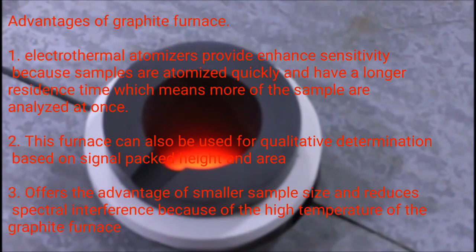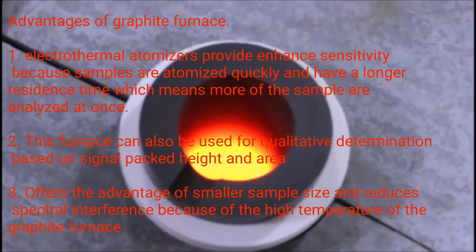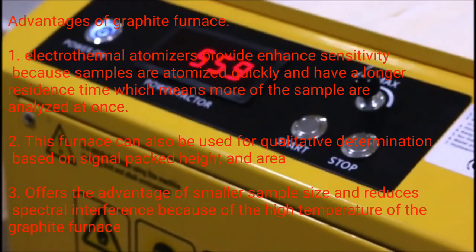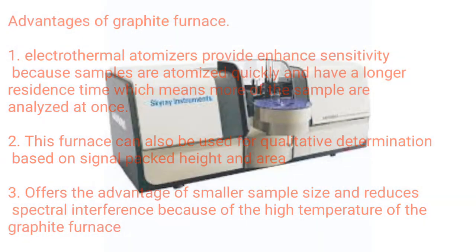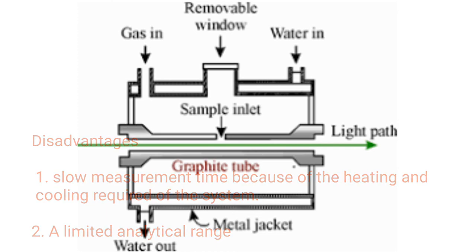A graphite furnace is generally considered an ultra-trace and micro-trace analytical technique with limits of detection in the low picogram range, precision of a few percent, and a dynamic range of about three orders of magnitude. Advantages: 1. Provides enhanced sensitivity because samples are atomized quickly and have a longer residence time, meaning more of the sample is analyzed at once. 2. Can be used for qualitative determination based on signal peak height. 3. Offers the advantage of smaller sample size and reduces spectral interference. Disadvantages: 1. Slow measurement time due to heating and cooling required. 2. Limited analytical range.